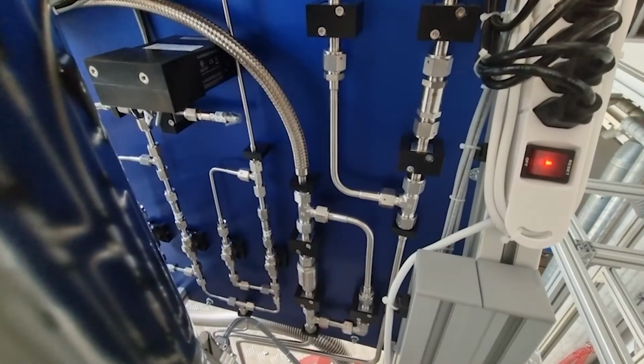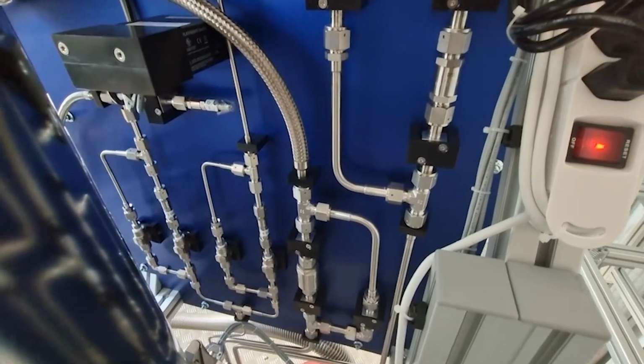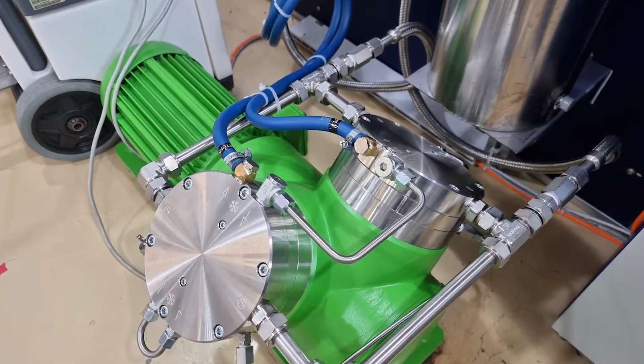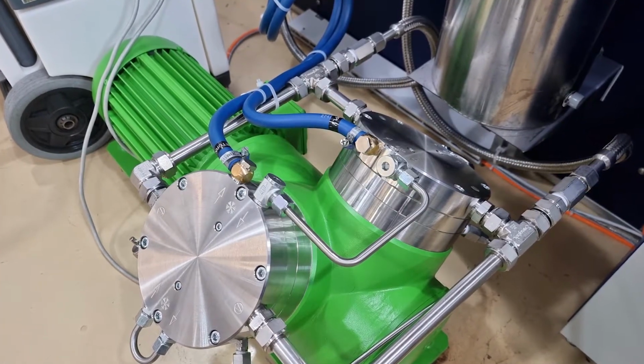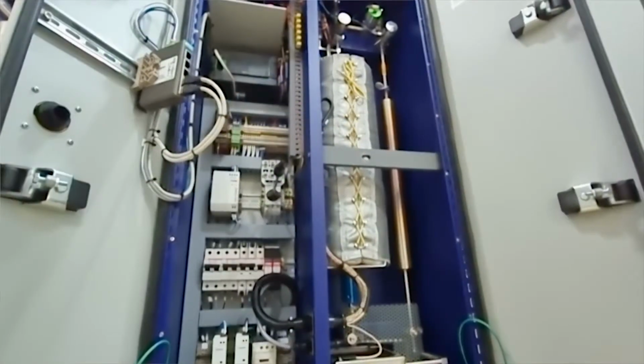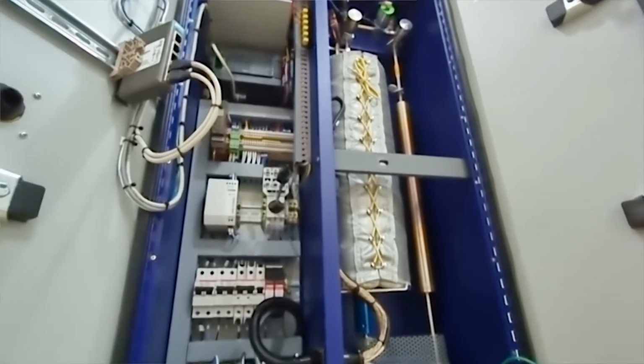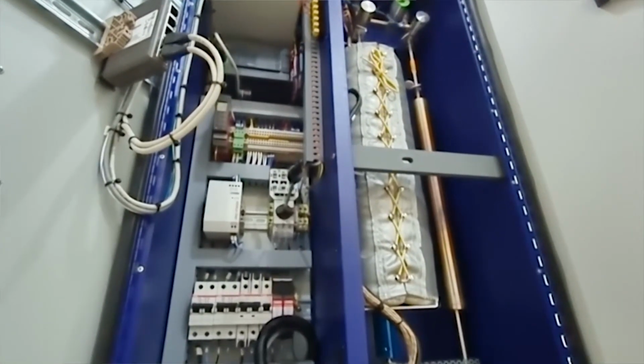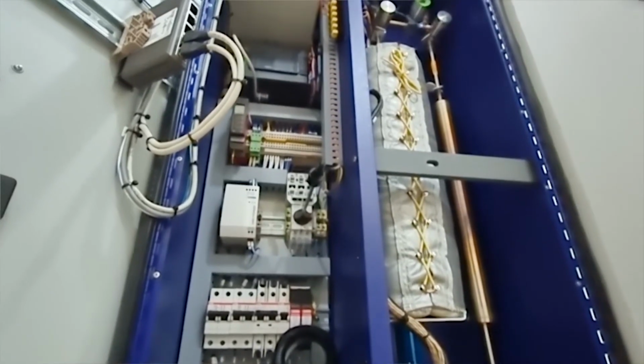The first is the purification loop. We use ceramic filters at the inlet and outlet of the heat exchanger to catch large particulates which could be present in the gas system. The xenon is circulated by a dual diaphragm compressor into a hot metal getter. The zirconium filter element is heated to 400 degrees Celsius and absorbs electronegative impurities, leaving the xenon gas with an impurity level lower than 1 part per billion.